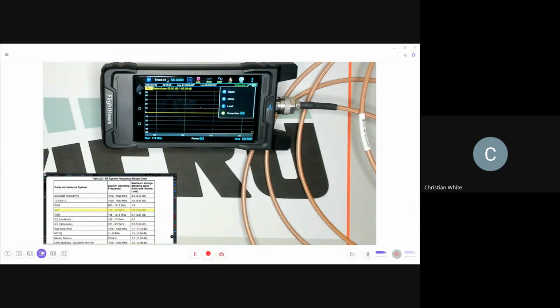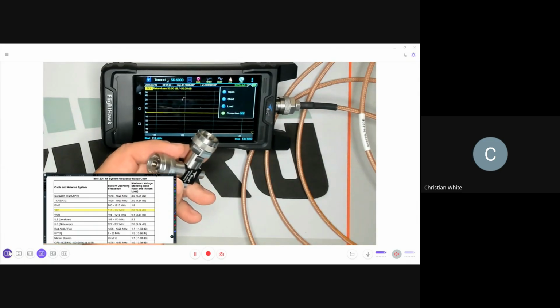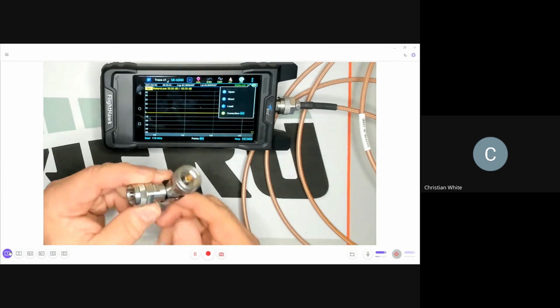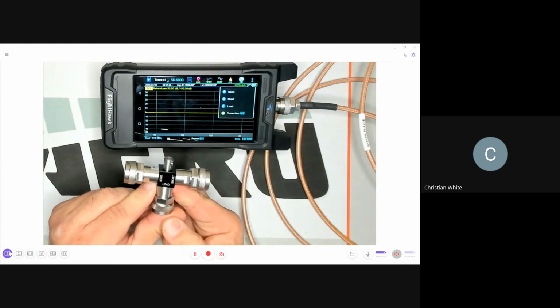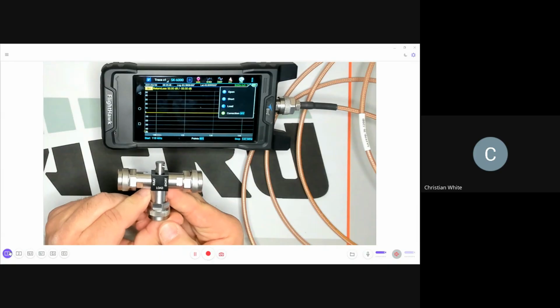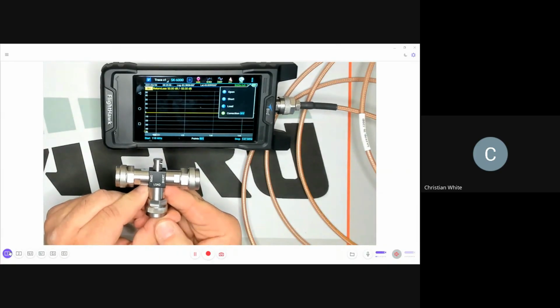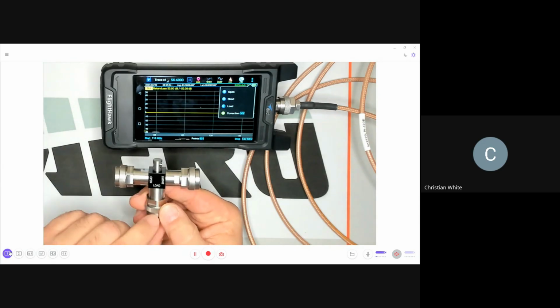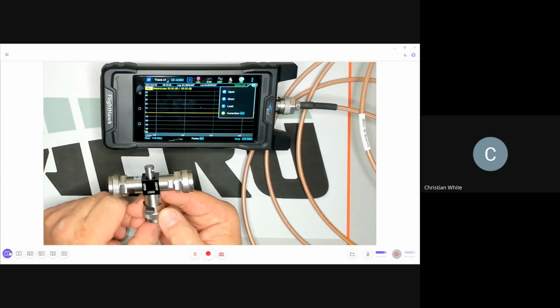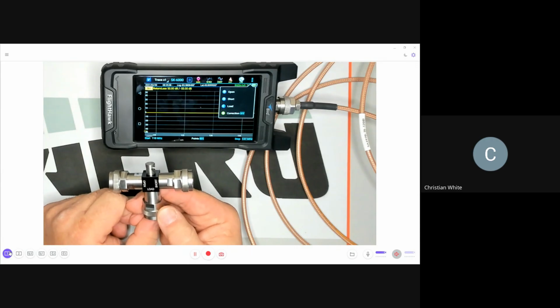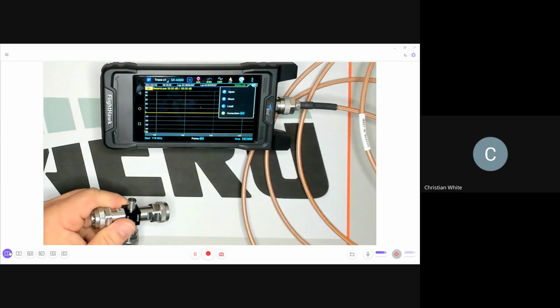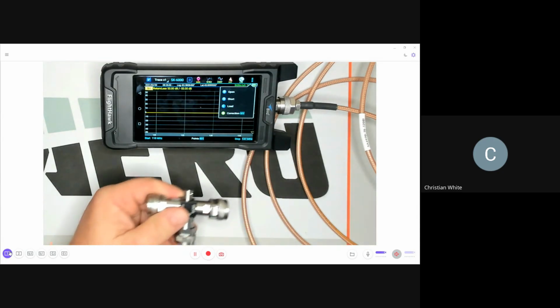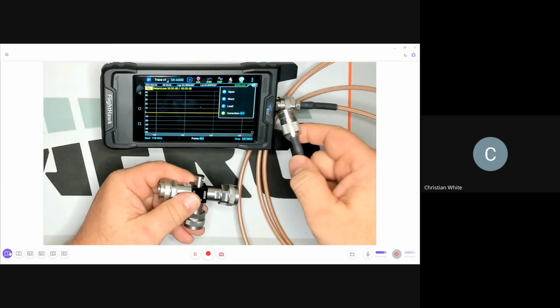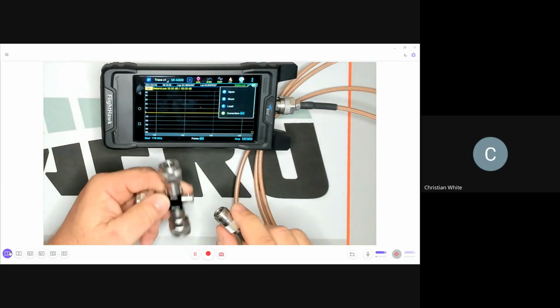And how we do a calibration is with this calibrated load, okay? So this calibrated load comes in the box. All we're gonna do, you can see on this calibrated load, it has an open, a short, and a load. So open, load, short, and we just connect that and hit the button. So in our case, the first one up here is open. So we're gonna take our cable that we already connected, and we're gonna go to the open one.